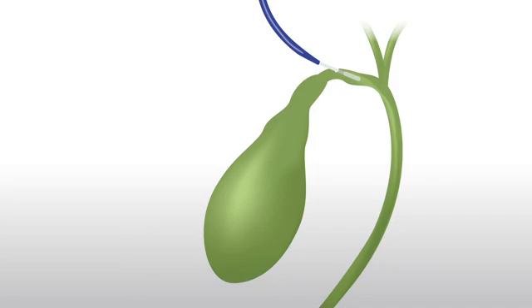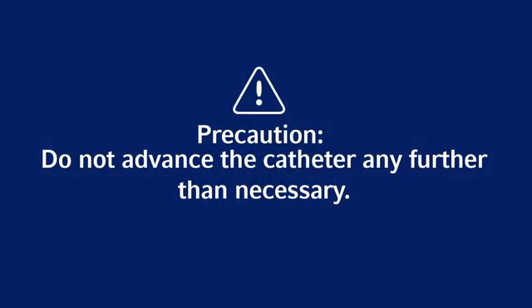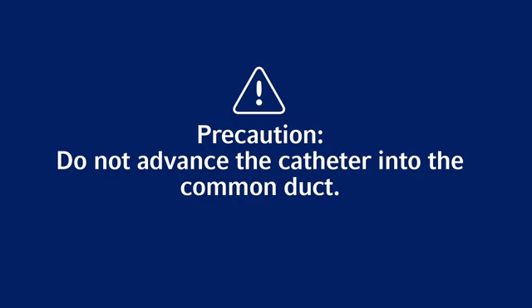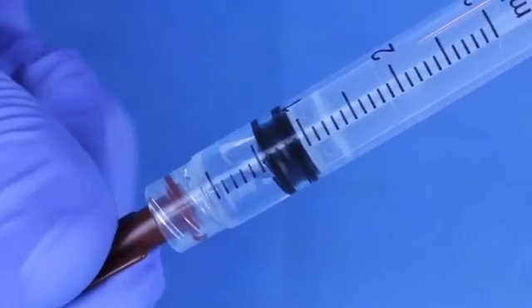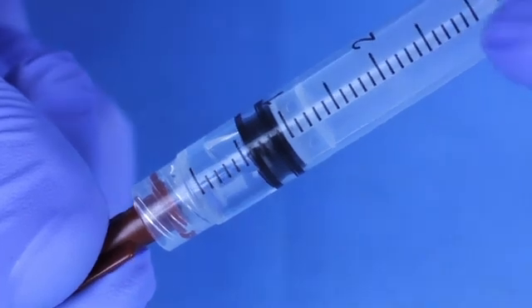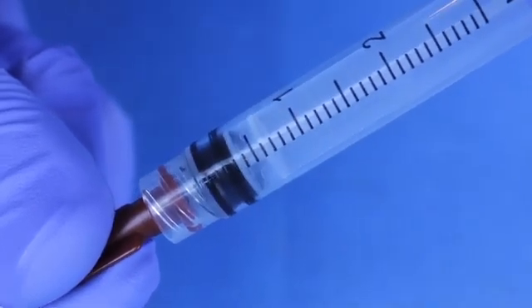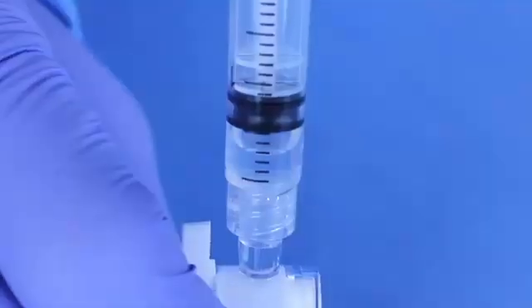To aid with placement, additional black bands are located at 1 cm intervals referenced from the proximal end of the balloon. Precaution: do not advance the catheter any further than necessary. Precaution: do not advance the catheter into the common duct. Inject saline through infusion port to verify that tip is not blocked by a valve in the cystic duct. If saline is difficult to inject, reposition catheter.